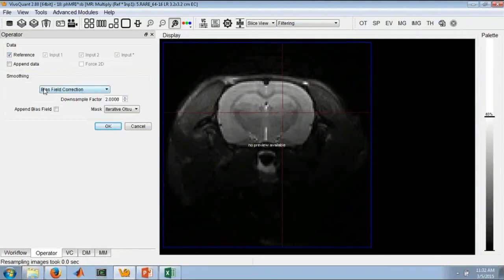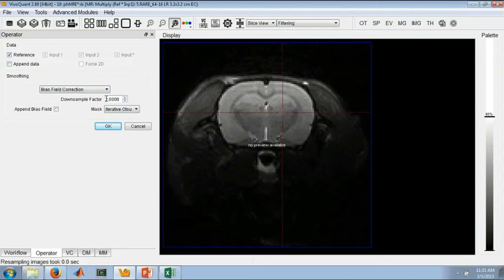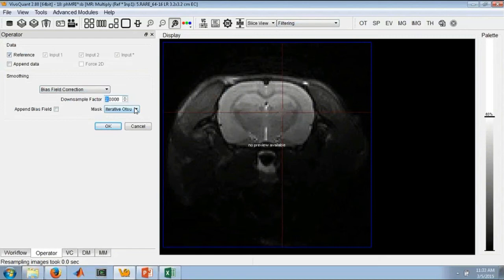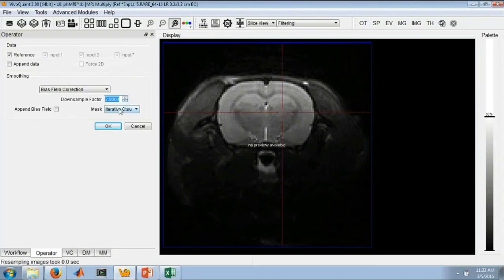Here what we can do is we have just a few options. If there are requests for additional settings to be made available, this is something that we may be able to do. Just please bring it up with your VivaQuant account manager. A down sample factor, this is simply just related to the speed of being able to perform the correction. If it's a very high down sample, it will be very quick, but it might not be quite as good. I find that a down sample factor of two works perfectly well.